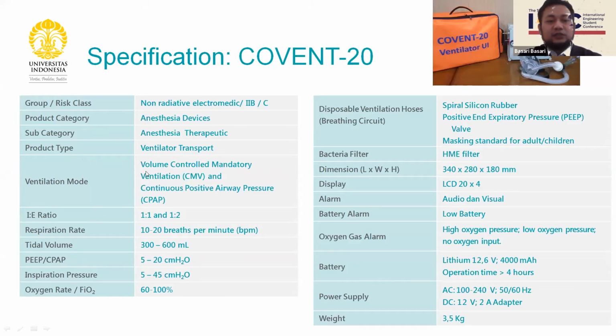The ventilation has two modes: control mode and CPAP mode, or supported mode. The control mode is volume control with mandatory ventilation, and then CPAP for CPAP mode. The inspiration to expiration ratio of 1 to 1 or 1 to 2 is mostly used in the current situation, with respiration rates only for adults. We are still developing; we can do it for children and even babies, but the requirements are stricter, so we focus on adults, with a tidal volume from 300 to 600 milliliters. For babies, infants or children, it is less than 300 milliliters.